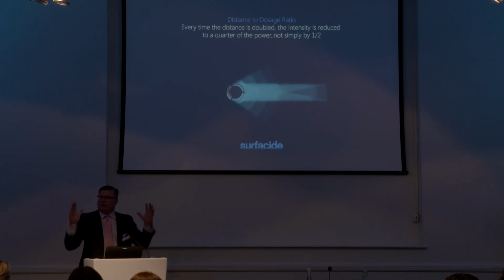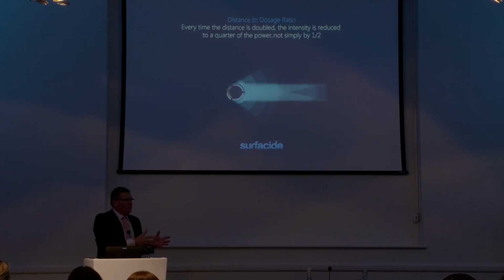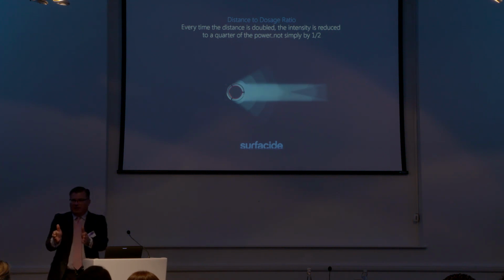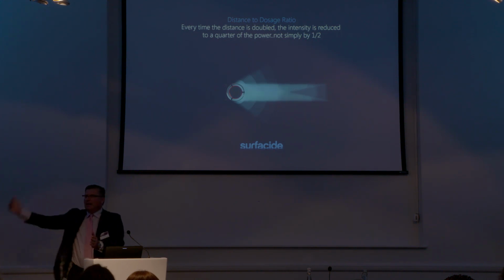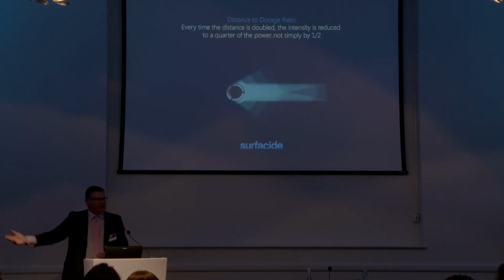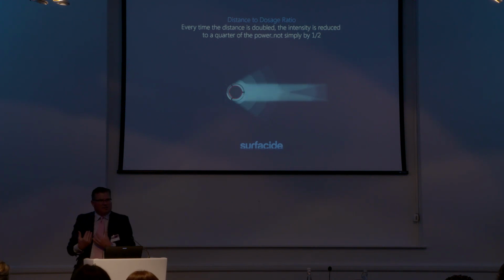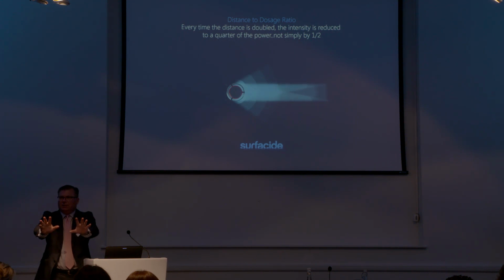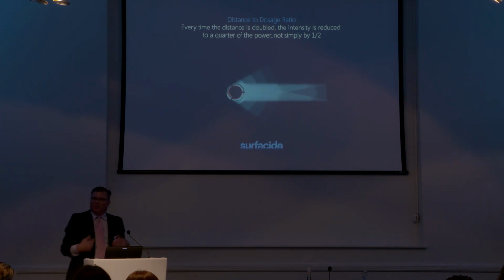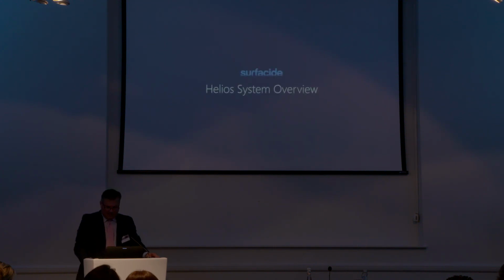Many rooms, we want to disinfect the whole room, but in a multi-bedded bay or in a ward, we have patient care areas that we want to focus the energy only where that patient care area is, not to the adjacent patients, not to the staff rearward. So our rear covering allows us to just deliver energy forward into a multi-bedded bay area. And I'll show you how that works in a moment.